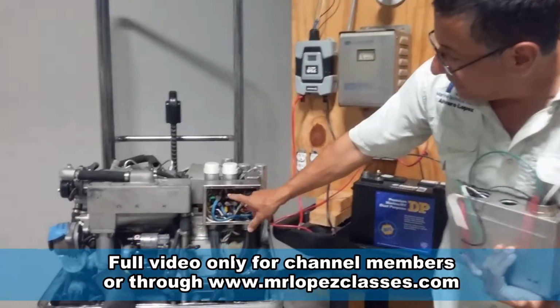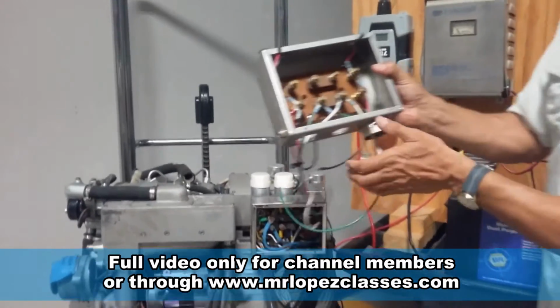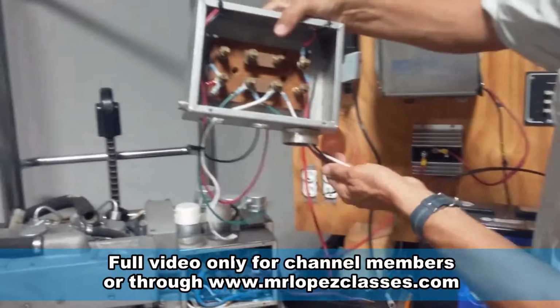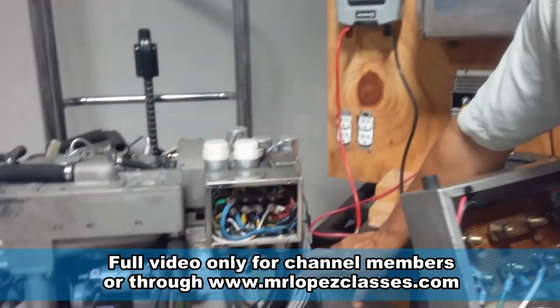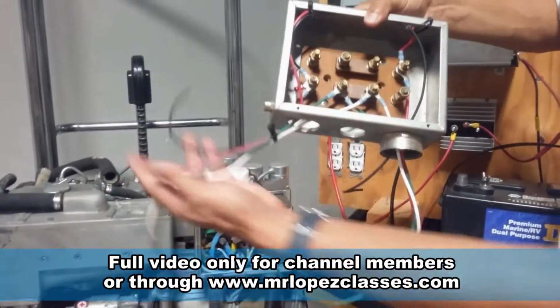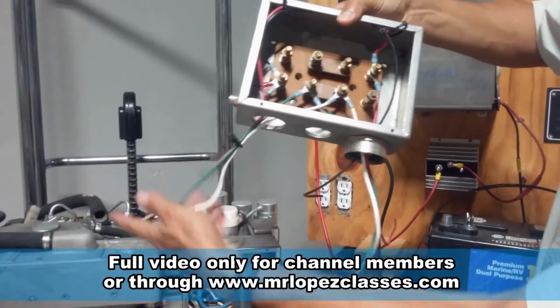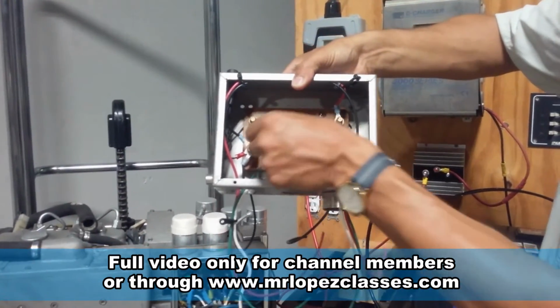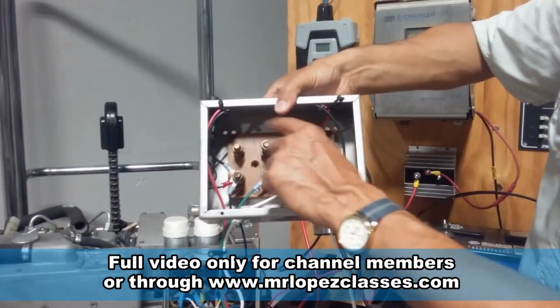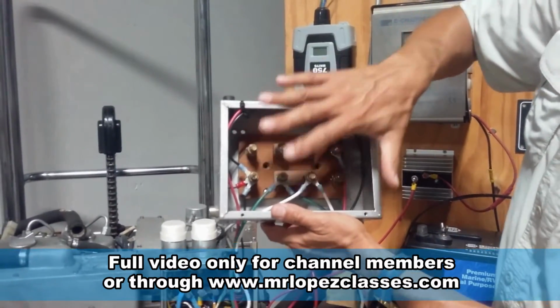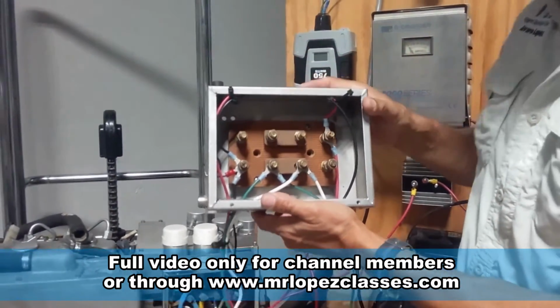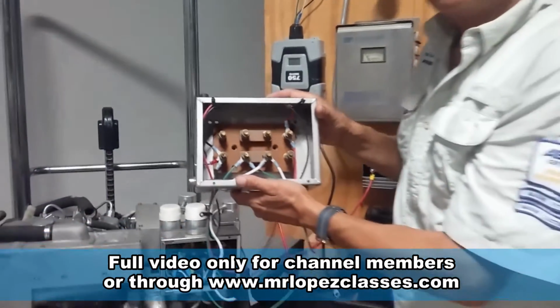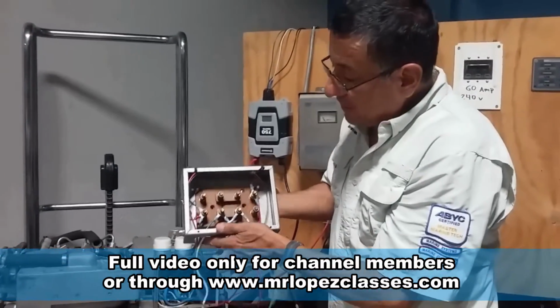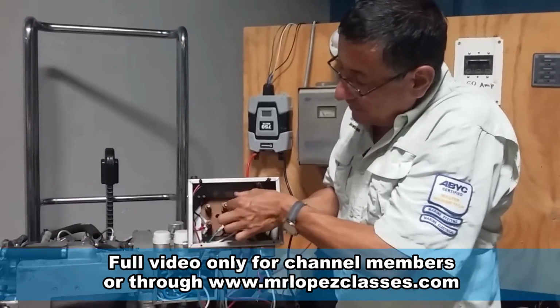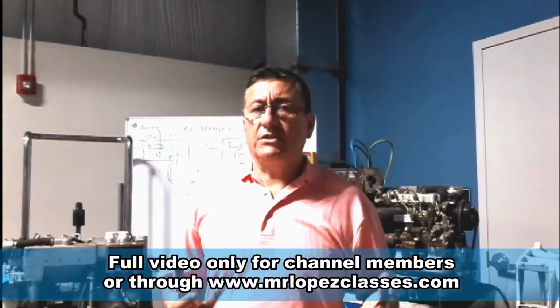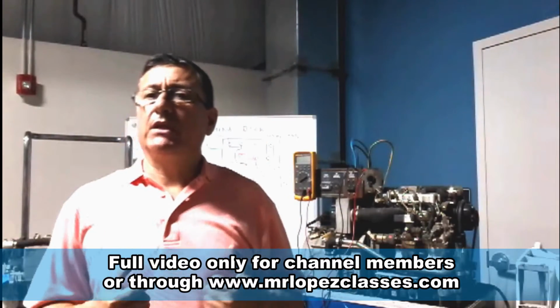The AC output panel board is basically this equipment. It's the element where the AC produced by the back end of the generator arrives. The hot, neutral, and ground enter in this panel board, and according to the configuration of the panel board, the generator can be configured for American power, European power, single phase, double phase, or three phase, depending on how the panel is configured. In what cases do you need to check the frequency?